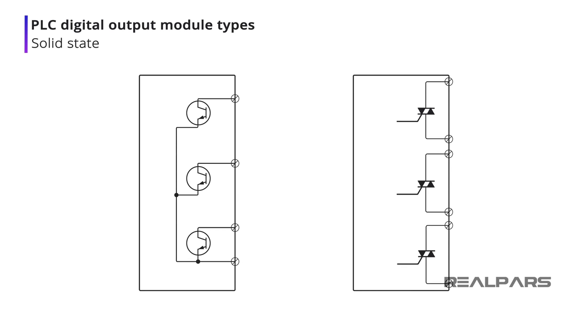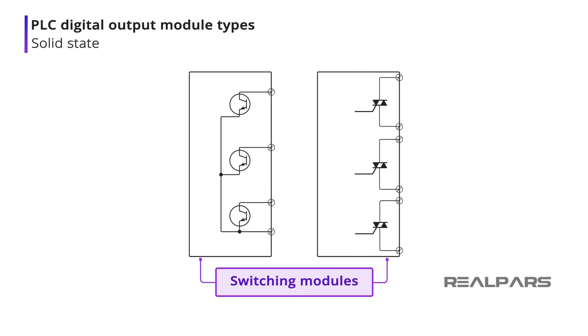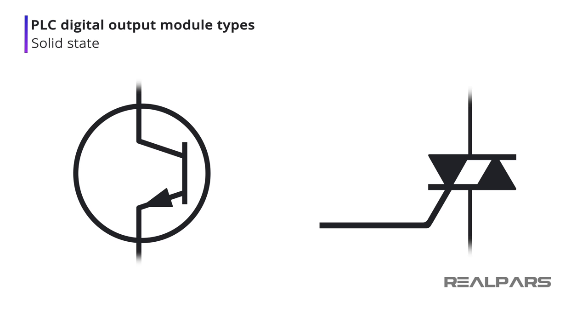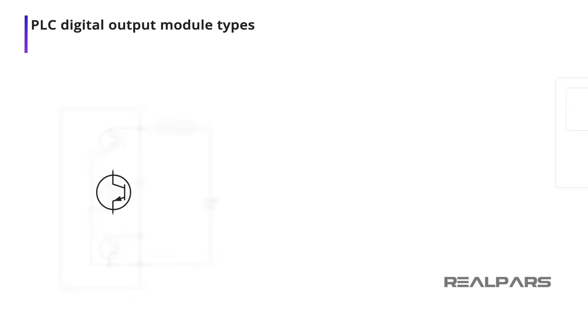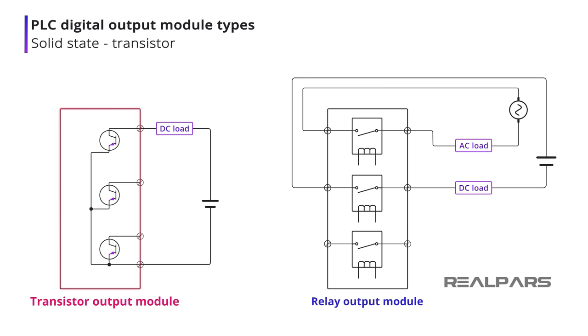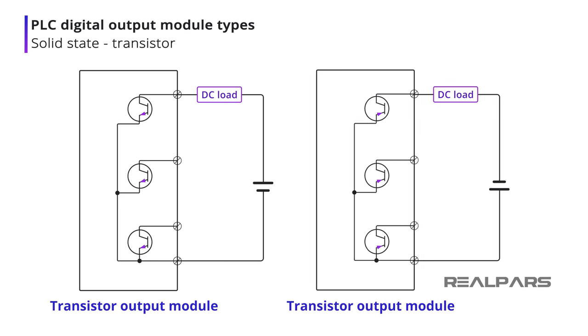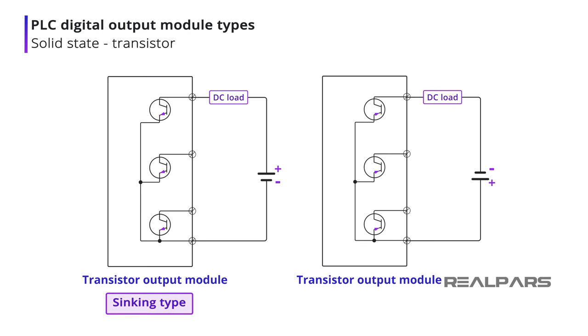Solid-state output modules are often referred to as switching modules. Output devices are turned on or off by using solid-state devices such as a bipolar junction transistor or BJT or a TRIAC. The transistor output module is voltage dependent and can only operate DC loads, unlike a relay output module that is happy to operate AC or DC loads. It's important that the load power supply is connected with the correct polarity, as the module can be either sinking type or sourcing type.